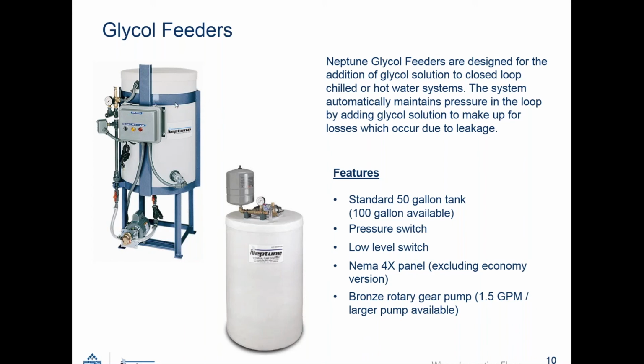We have two different versions. We have the sturdier and more popular G series, which comes with a NEMA 4X panel with a pressure switch that activates. You can see the pressure switch is here and your outlet comes out this way into the system. These are generally set standard at 12 psi to turn on the pump when leakage occurs and shut off at 30 psi. There are other ranges beyond that that are field adjustable. And if this pressure switch doesn't satisfy your needs, we can source other pressure switches, up to 100 psi.